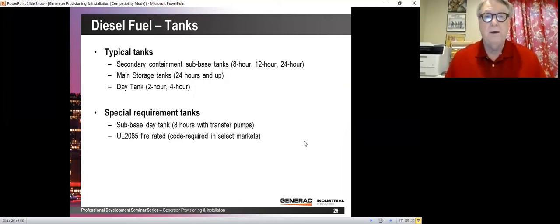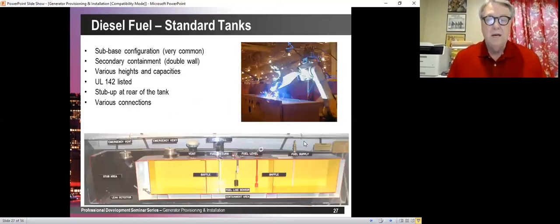Typical tanks are 8, 12, 24, but tanks are all over the place, and it depends upon the base size of the tank. And typically tanks are actually 12, 24, and 36 inch, but they could be 30 inch. And think about the tank. If you need a 24-hour tank, fine, get a 24-hour tank, but now you've got 24 hours of fuel to maintain. If you don't need a 24-hour tank, think of getting something smaller that might have less fuel that you're going to have to maintain.